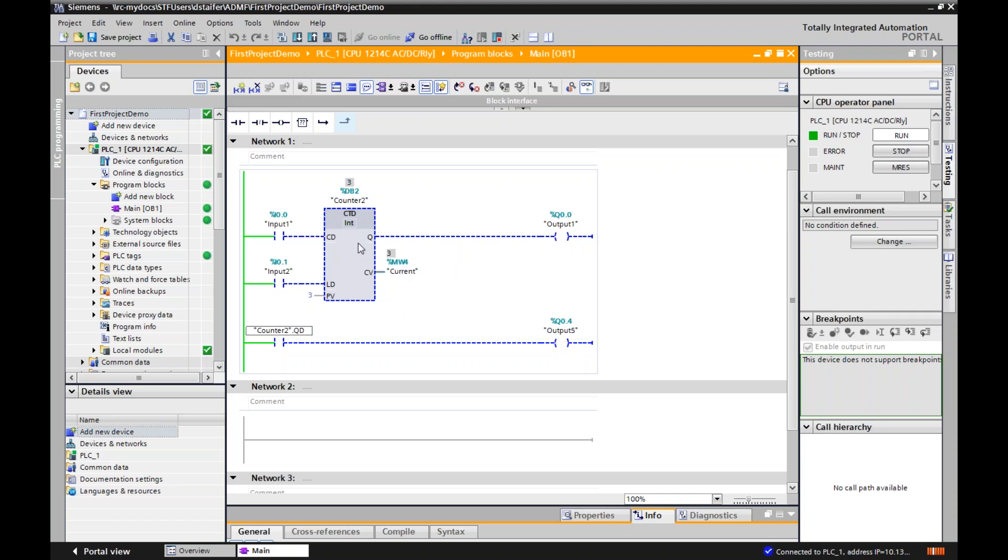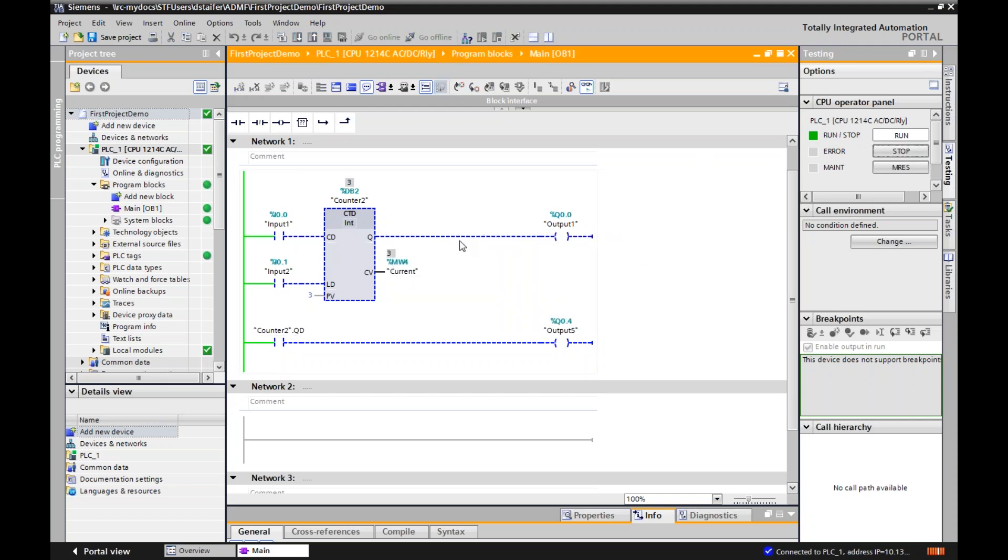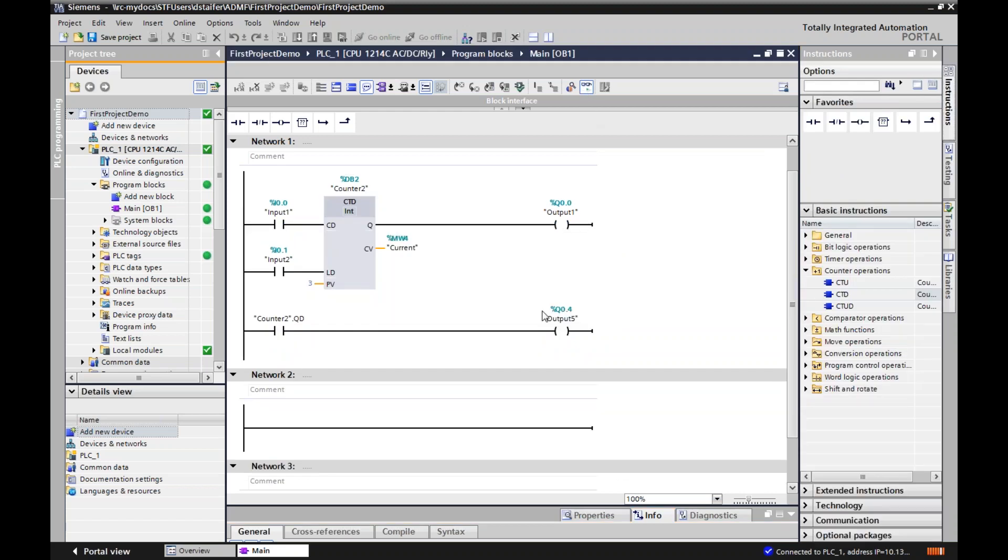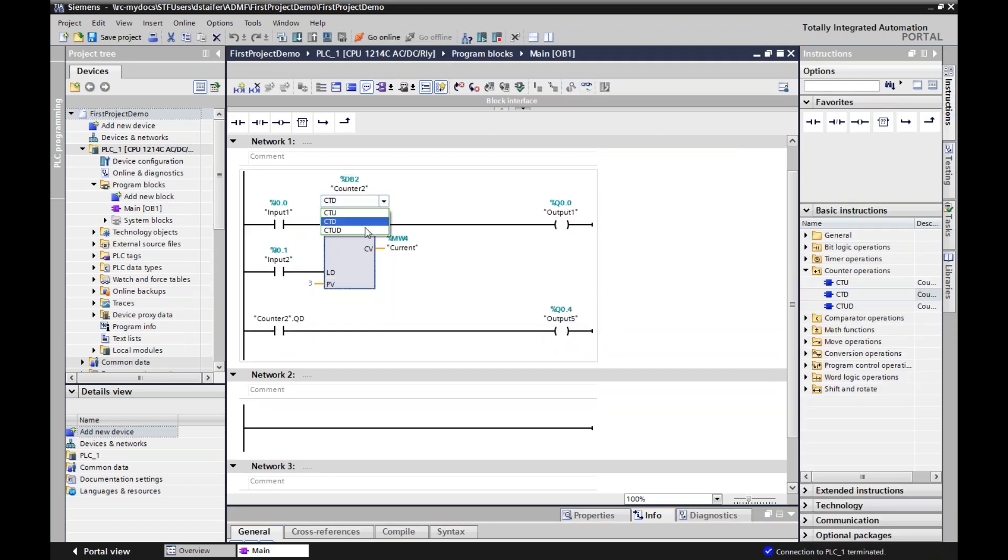Here's my load. Let's see what happens. And now notice I'm not subtracting because, once again, load is dominant over the countdown. And so when you're working with a countdown, it's dealer's choice whether you count up from zero, hit a preset, and then turns on a Q, or if you count down to zero, and then once zero's hit it turns on the Q, the output. It's really up to you. It depends on the application. Both are in your toolbox.